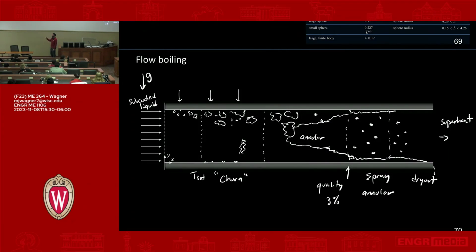If you have really low velocities, that is, a really low heat flux relative to the diameter of the tube or whatever it is, your annular flow is going to be mostly liquid on the bottom and maybe steam on the top. You don't really get an annulus, you maybe get stratification. But for most reasonable boiling applications, this is what you're going to tend to see. And you're providing this flow in, and it's maybe not a large velocity to begin with, but by the time you're at this annular region, it's really moving because you have a lot of low density steam moving through the pipe. Good question. Anything else? Other questions?